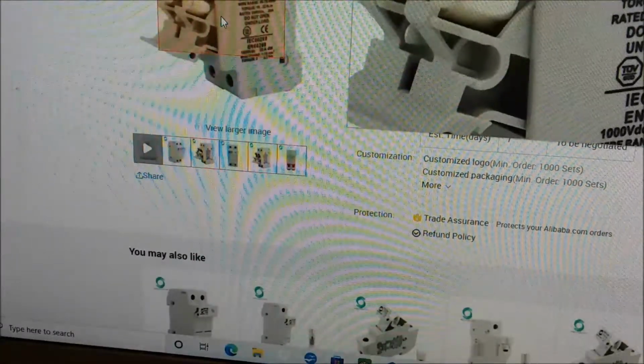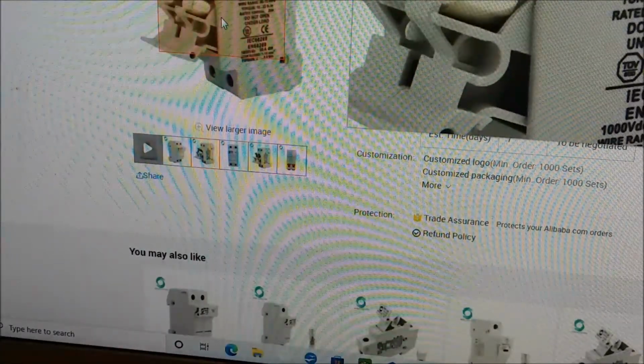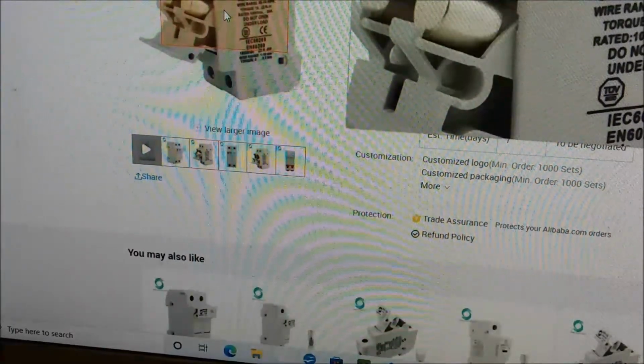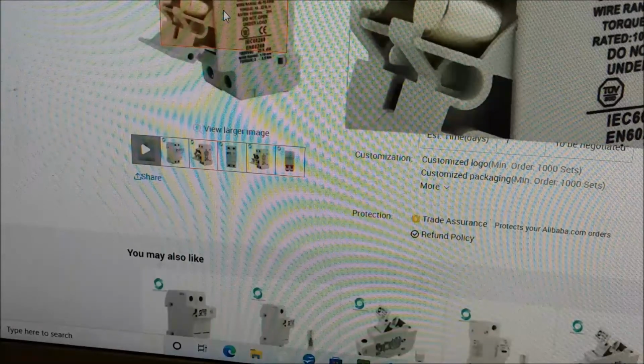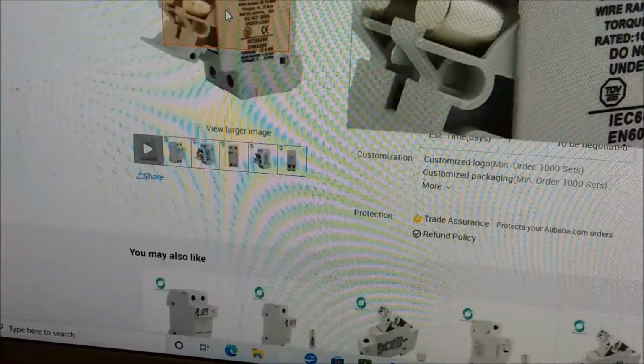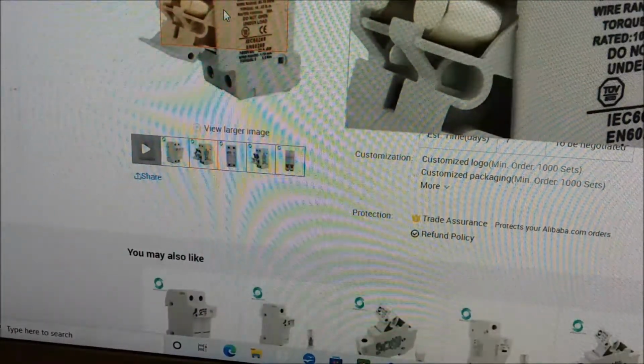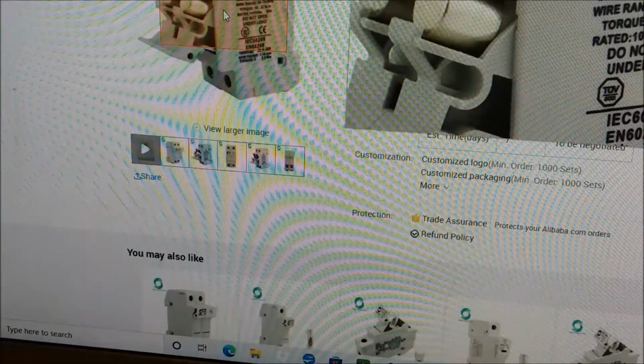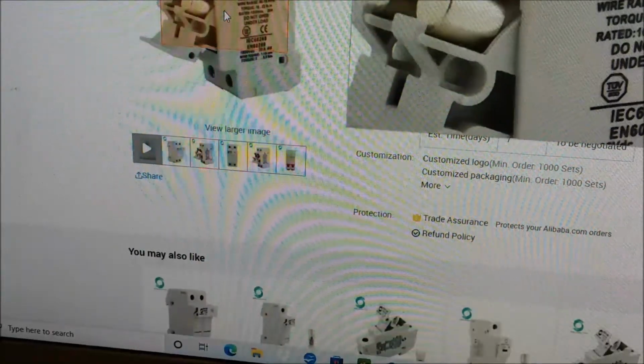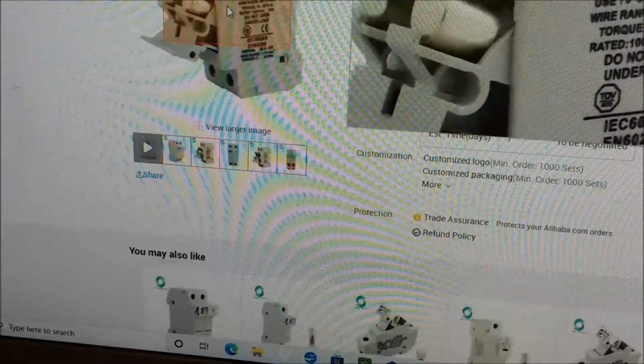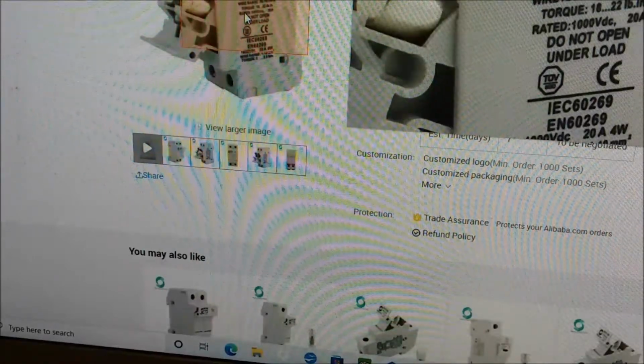Okay, and we know what kind of part numbers we're looking for. That's a $265, 14 circuit box. It's available for $180 with 8 circuits - that would be 4 on top, 4 on the bottom. If I wasn't wanting to put lightning protection inside the powerhouse, the 8 circuit would have been fine, more than I need. But I only need 7 outside and 7 inside, so the 14 circuit one is perfect - no spare parts.